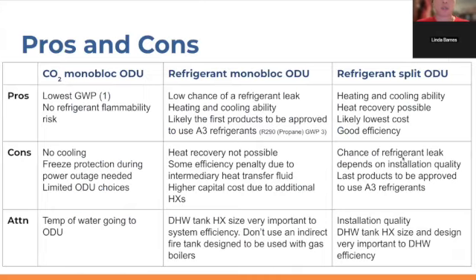And so, to recap some of the pros and cons of the different types of combi heat pumps, the CO2 systems have the lowest global warming potential, since you'd be using CO2. CO2 also has the advantage of having no flammability risk. But one of the cons of this category is that currently the products on the market can't do cooling. Typically, these systems use just straight water going to the outdoor unit, and the reason is because the CO2 refrigerant has the capability of achieving what's called a very high lift, meaning that it can heat water from, let's say, 50 degrees straight up to 130 degrees in one go. And the CO2 refrigerant cycle is actually the most efficient when the incoming water, or whatever that heat transfer fluid is, is quite cold, and it's typically just straight water coming in quite cold.